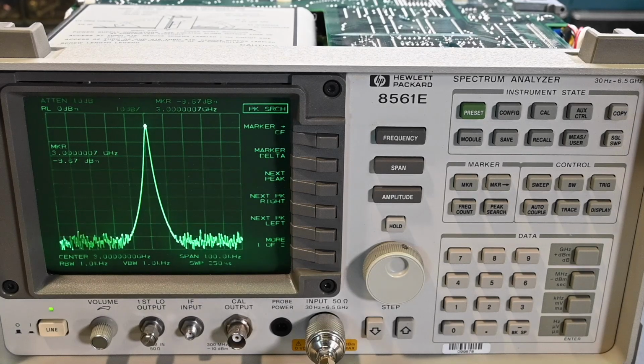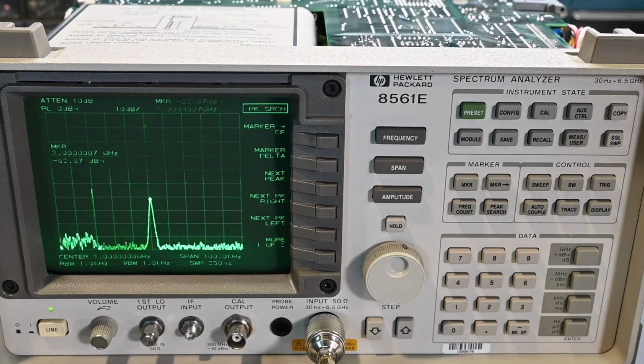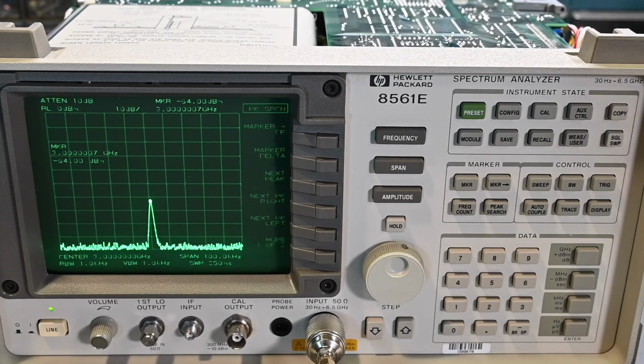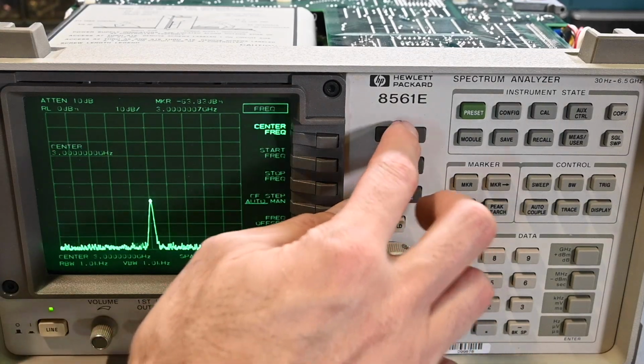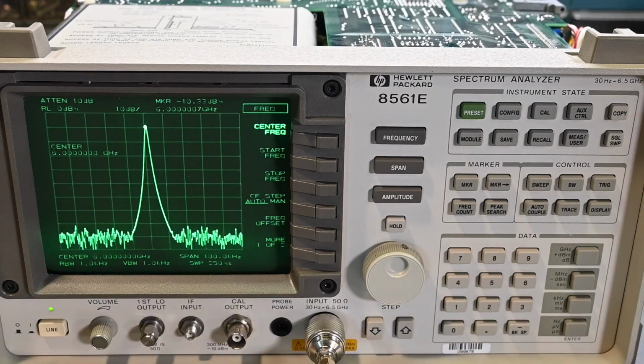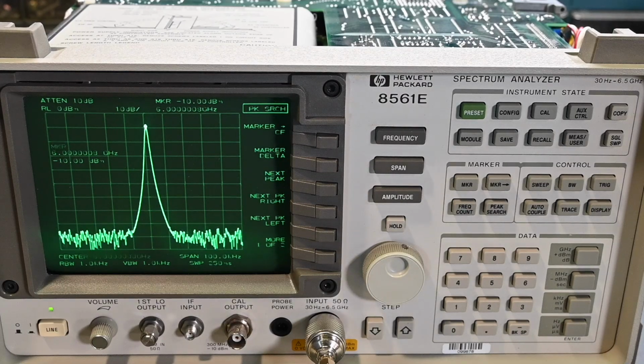So let's try 6 gigahertz. So jump over here to the signal generator, go to frequency 6 gigahertz, and correct the level so we compensate for the coax. So let's see, here we go, frequency 6 gigahertz. And let's do a peak search. Span is still at 100 kilohertz. And that's spot on, look at that. Minus 10 dBm. Perfect. So this spectrum analyzer is functioning very well. So calibration successful and repair successful.